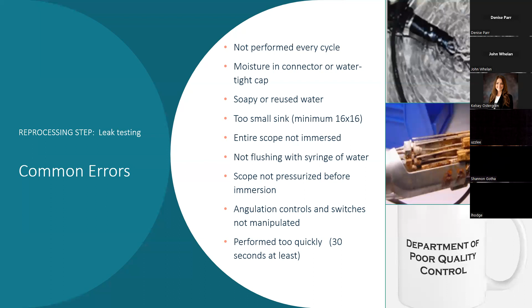Faulty leak testers are both a device and an infection risk. Not only can fluid get inside again, but bioburden can as well. So if the leak tester is not supplying adequate pressure, leaks can be missed. The leak tester may be making a noise. It may sound like something's working, but it may not be putting out a correct pressure. A common leak tester still in existence for those customers that have Olympus scopes is what you see in the picture here. It's a base unit, a pump, and a black cable. It's the Olympus MU1 and MB155 leak tester setup.